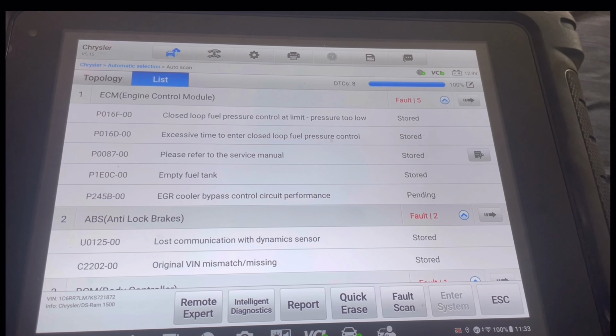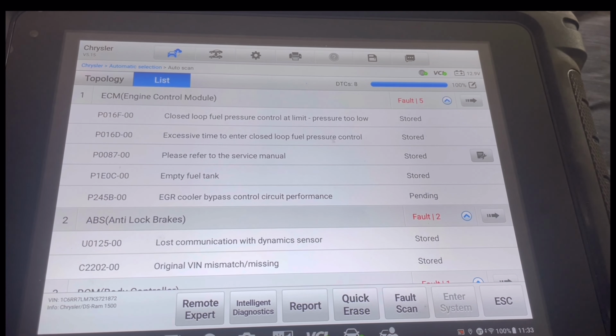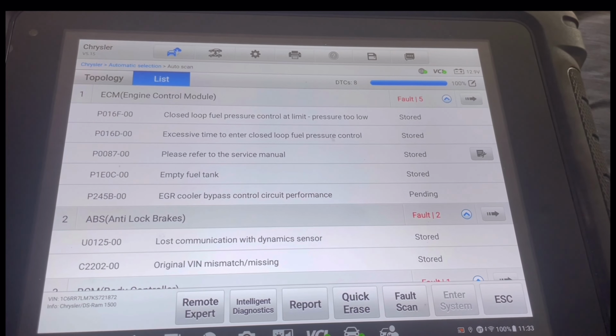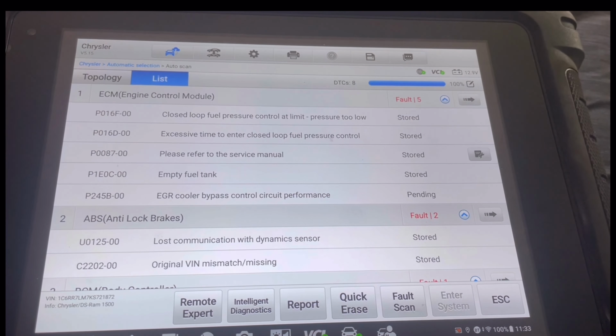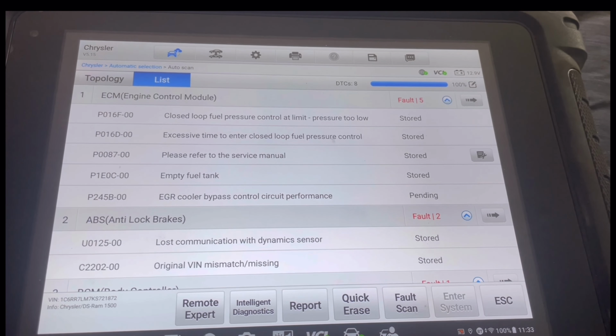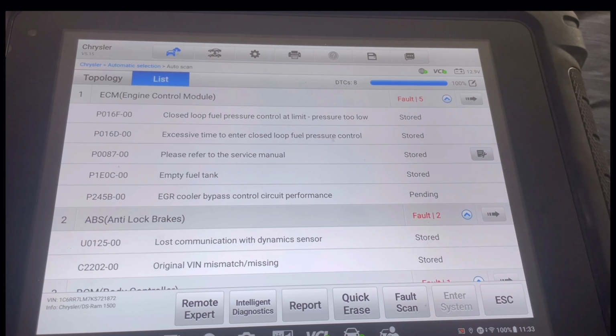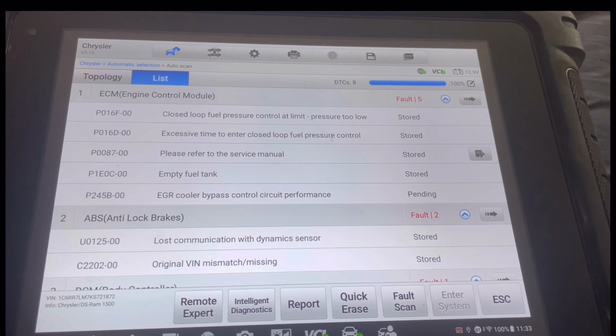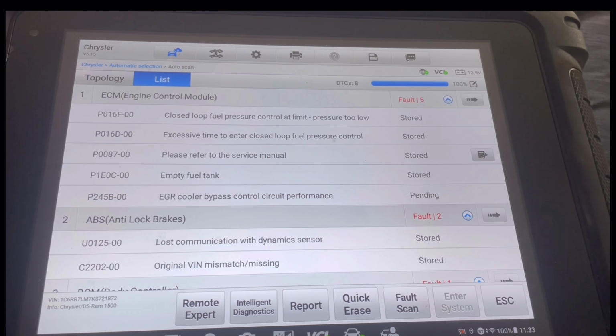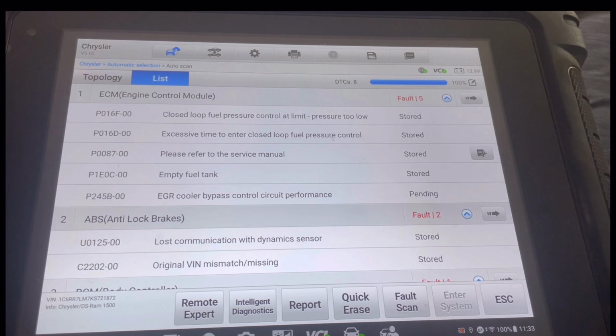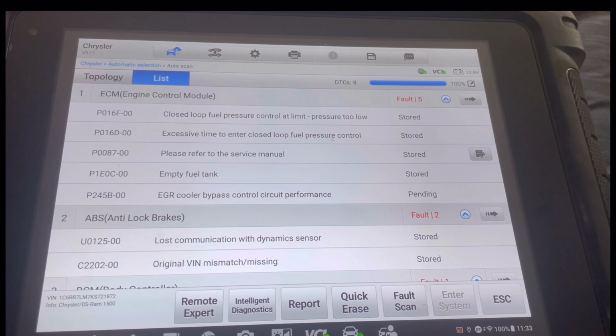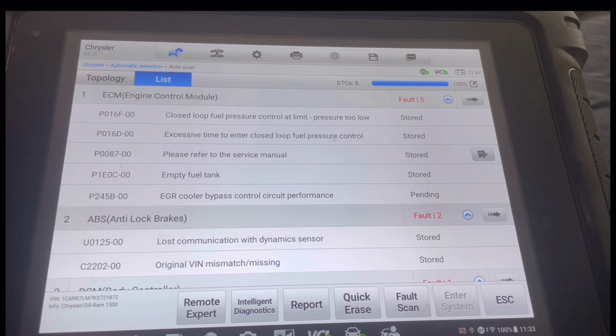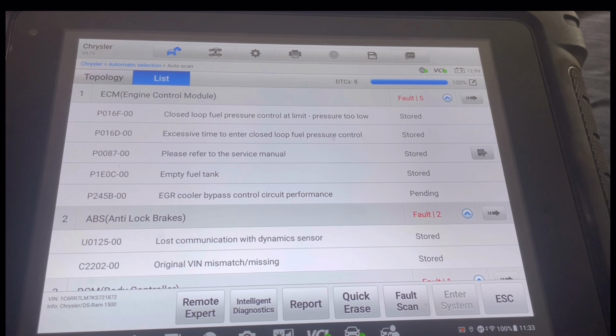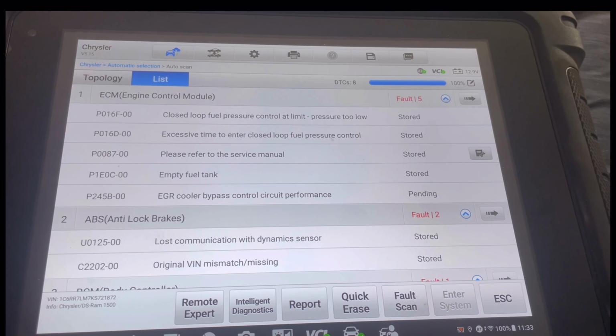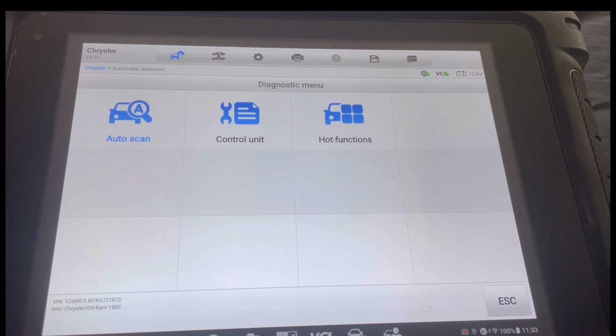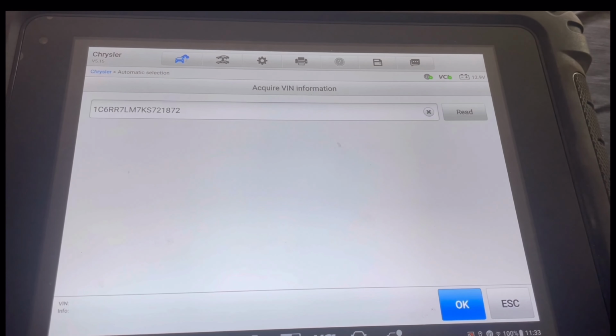We're currently connected. Our ECM is broadcasting 5 different faults, 4 active and 1 pending. We're showing a P016F, pressure too low in the common rail; P016D, excessive time to enter closed loop pressure control, meaning it didn't see the pressure in time; P0087, refer to service manual; and a P1E0C, which says empty fuel tank. Lastly, a permanent or pending code, P245B, EGR cooler bypass. So I think we should dig into this a little more and look at the EOBD diagnostics menu.